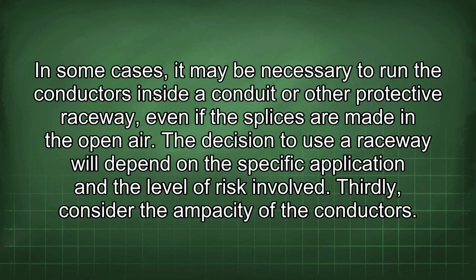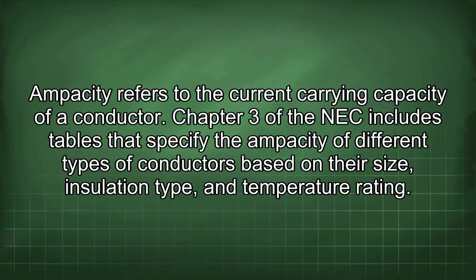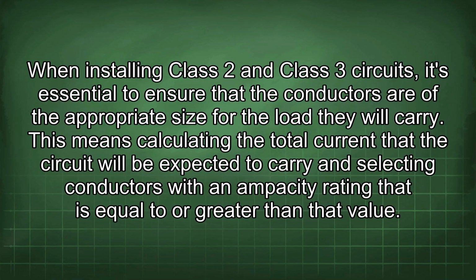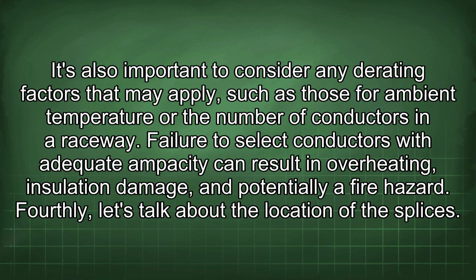Thirdly, consider the ampacity of the conductors. Ampacity refers to the current carrying capacity of a conductor. Chapter 3 of the NEC includes tables that specify the ampacity of different types of conductors based on their size, insulation type, and temperature rating. When installing Class 2 and Class 3 circuits, it's essential to ensure that the conductors are of the appropriate size for the load they will carry. This means calculating the total current that the circuit will be expected to carry and selecting conductors with an ampacity rating that is equal to or greater than that value. It's also important to consider any derating factors that may apply, such as those for ambient temperature or the number of conductors in a raceway. Failure to select conductors with adequate ampacity can result in overheating, insulation damage, and potentially a fire hazard.